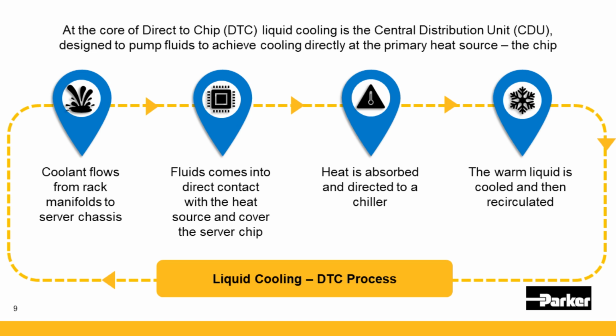Either it's single phase, doing it directly through a heat exchanger - maybe a rear door heat exchanger in an environment without access to a lot of cooling water - or it could be tied into facility cooling water for a major installation. Then that water comes back, and the process continues.